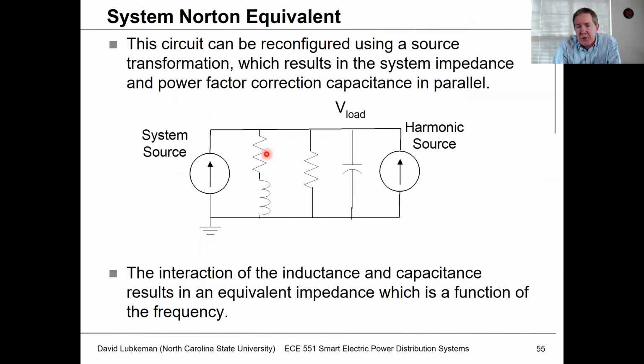This is a current in parallel with impedance. And what you see is you have both of these current sources injecting into an equivalent impedance where you could have a lot of inductance associated with it. You have resistance and you have capacitance. And whenever you have a parallel combination of inductance and capacitance, then you have potential for what we refer to as resonance. So there could actually be a situation when these capacitors and inductors are in parallel that we could get an impedance that's pretty high at certain frequencies. And if we're injecting a harmonic at a resonant frequency of the circuit, then overvoltages could occur.